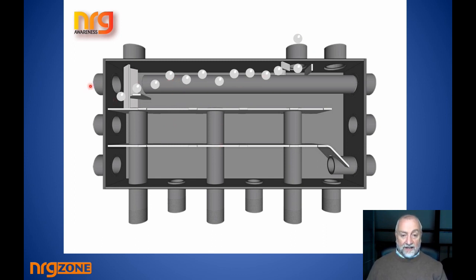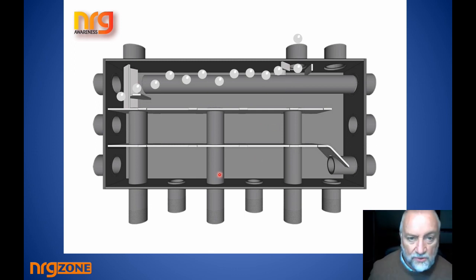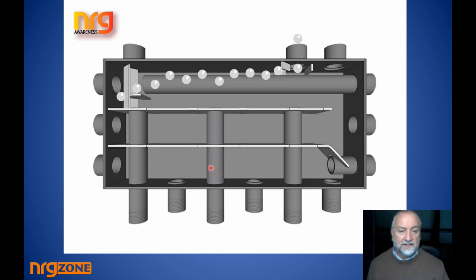So in effect you have an elongated, very useful, very long air trap, and if the air isn't caught on the way out, when it comes back from the zones it's caught again, and if there's anything coming back or trapped in the middle chamber, they all allow the air to drift up to the top chamber. So that's why it's so rapid and so effective at deaerating systems. So it's not just confined to this little corner.